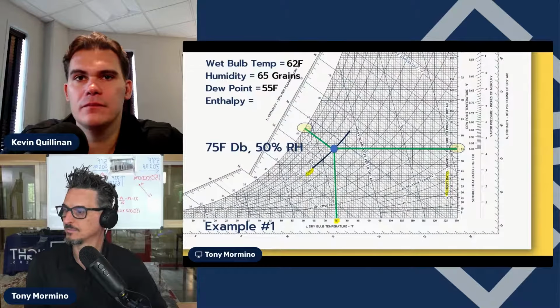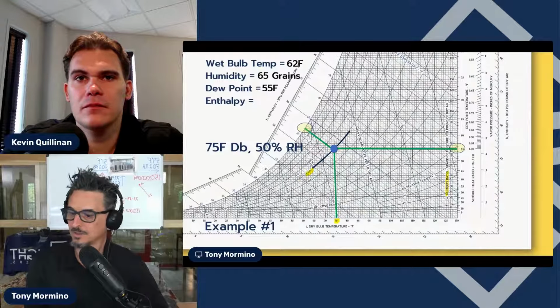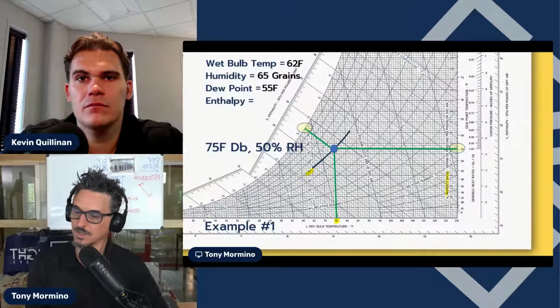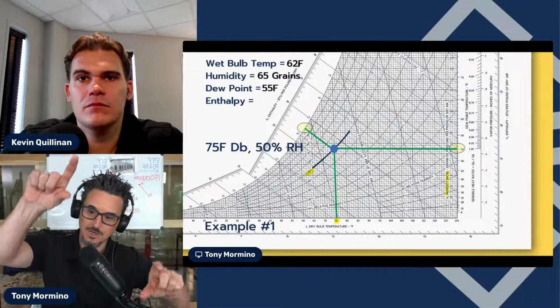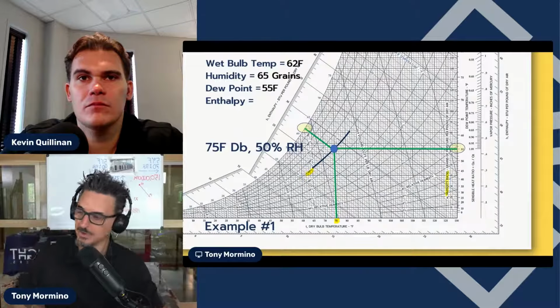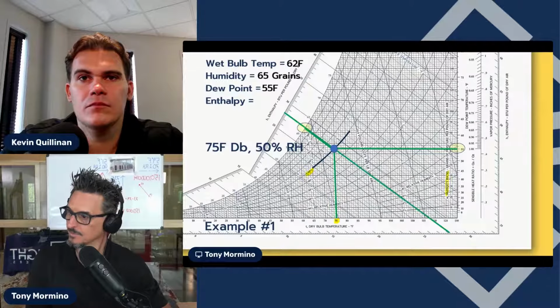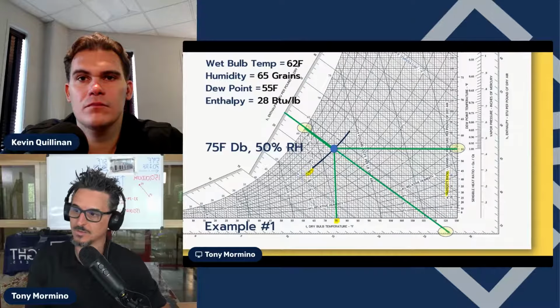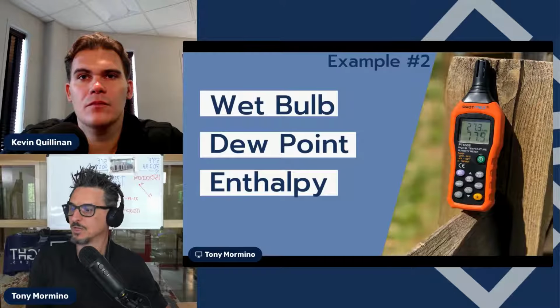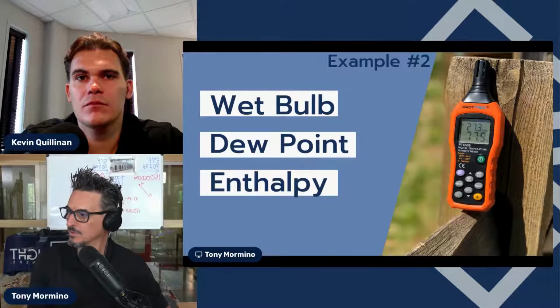And then to get the enthalpy, you take your straight edge, drive it through that point in a way that it lines up. You got to do a little bit of this action so it lines up on the enthalpy, and you get your enthalpy, something like that, which is 28 BTUs per pound. Why don't we do one more of those because we're getting a little long on time, and then we'll see if anybody has questions.